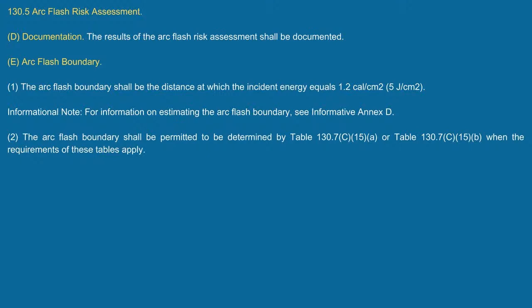And the other day I made a post that we're on the big attorney network now as experts on the NEC and NFPA and OSHA standards and everything, recommended now in cases like this. Well, we went up against OSHA, and I wrote a report, and I said, no, actually the table value is the second option. The first option is being able to use the cal rating, arc flash boundary, and everything that's calculated in Annex D. And if you look here, E1 is the first one that's listed. E2 is the second one, which is the tables.